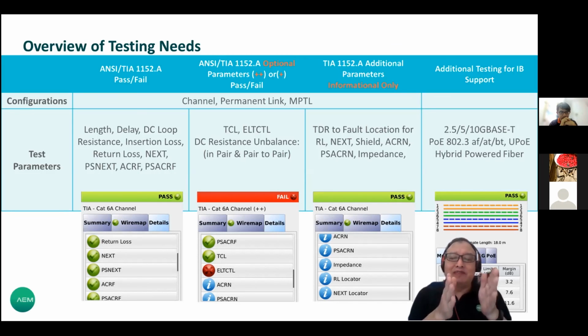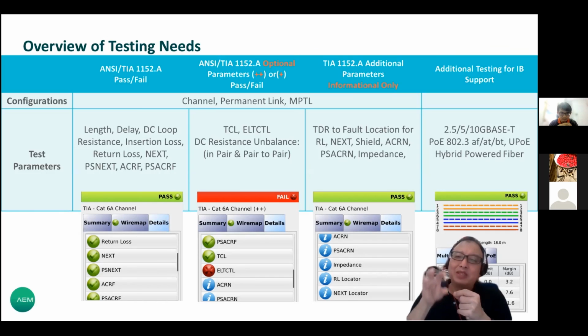You can see the first column and the second column. The first column says TIA Cat6A channel, the other column TIA Cat6A++. These two different settings allow you to test the TCL with a pass or fail. The ++ is an option for the user to decide. If they want to measure this additional parameter and make sure it also passes, they have to select the ++.